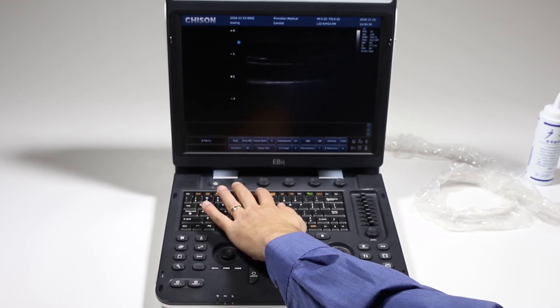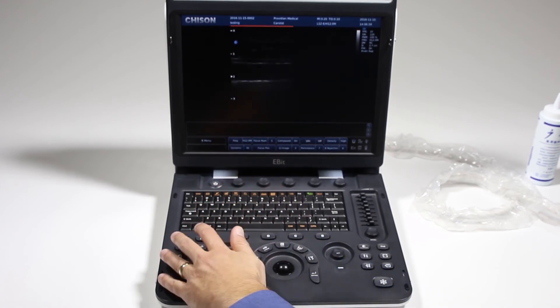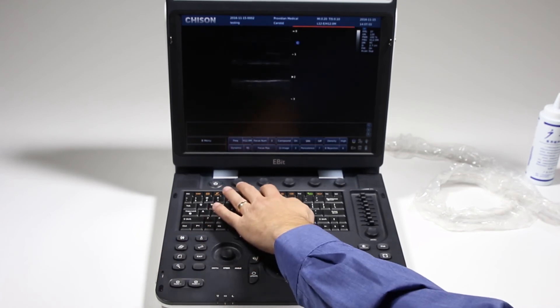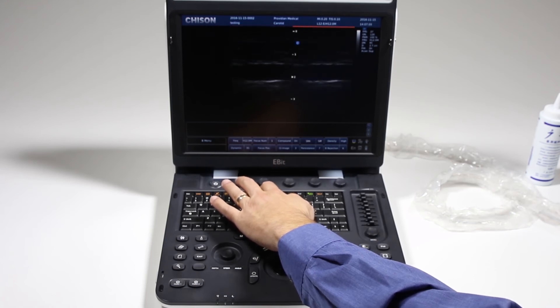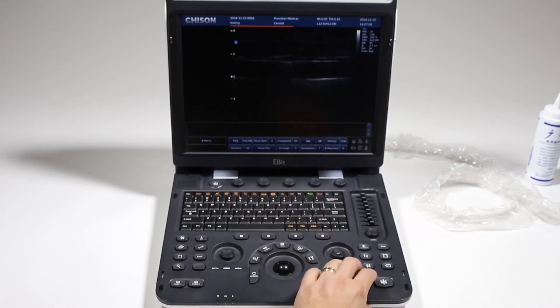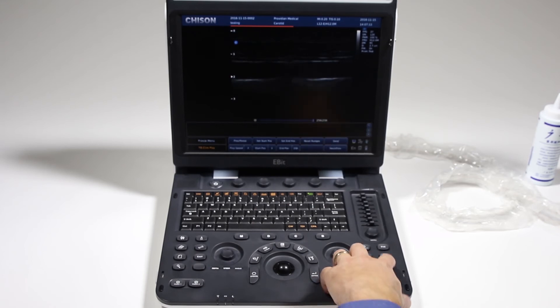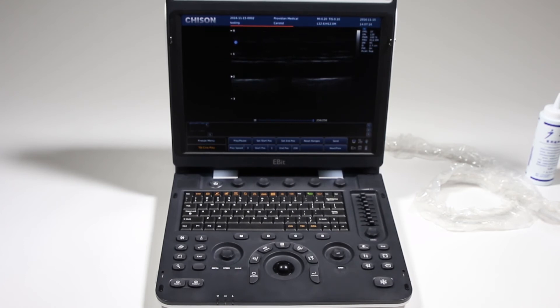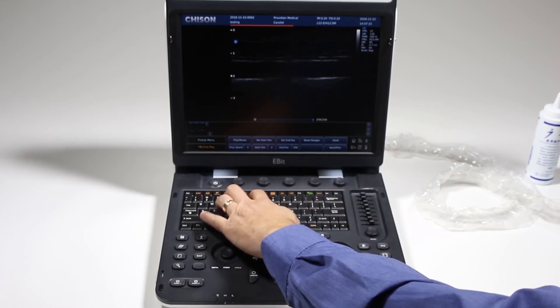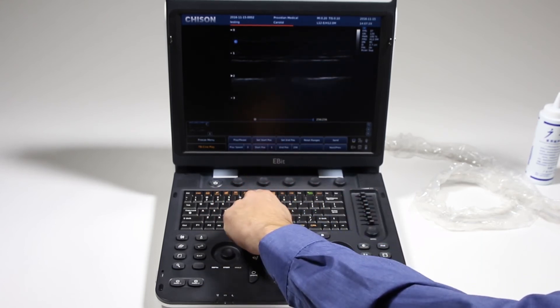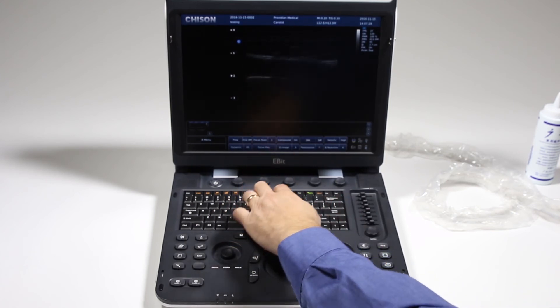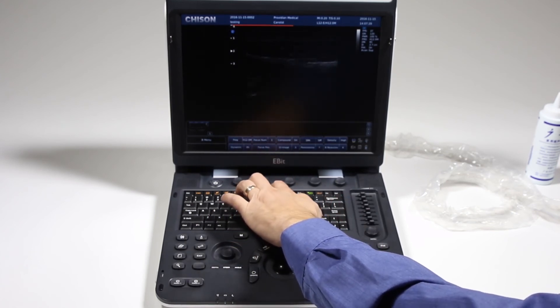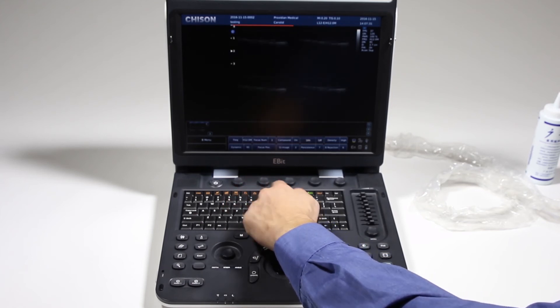Now we have the dual screen. I'm going to click it and I'll get the image on the left. Press it again to get the image on the right and I can just go back and forth here to switch between the live images. When I'm ready to make a measurement, I can hit freeze and then save that image by pressing the save button and it will show up in that thumbnail down there. Same thing works for quad screen. If I want to go back, first the full screen, I can click this here on freeze. Click that and it's going to take me back to the full screen. The quad screen works the same way.